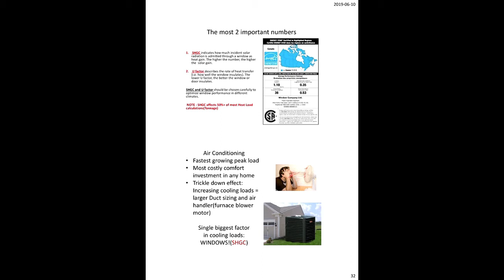This is a little study that was done. A new design manual was done by the NRC. It would be actually really useful for you folks to have a look at. It's going to be available within the next month. It's called Mechanical Design for Low Load Housing. And it identifies things like if you have a solar heat gain of 0.3, which is called mid-range, if you get higher than a 0.61, you can increase your tonnage by a half ton to a full ton just on a townhome.